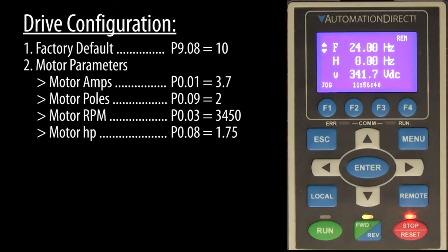These are the parameters I just entered for my motor and drive controls. Yours will probably be different. Notice that because I'm using this 3600 RPM jet pump motor, I had to set the number of poles to 2 before I could set the RPM above 1800.